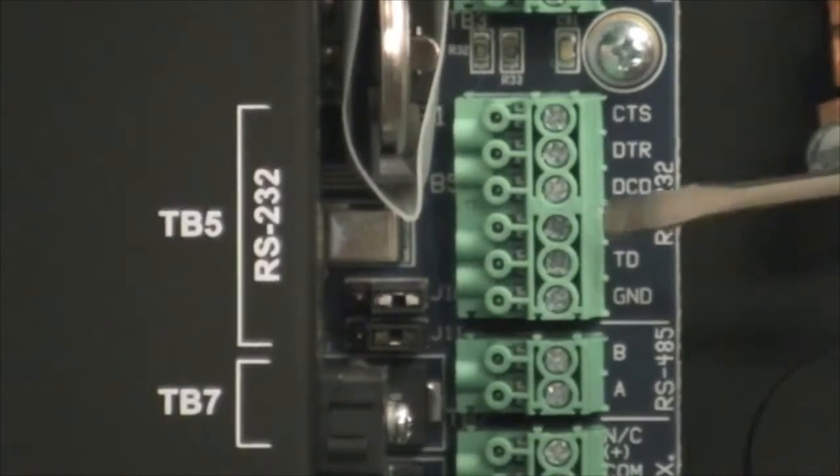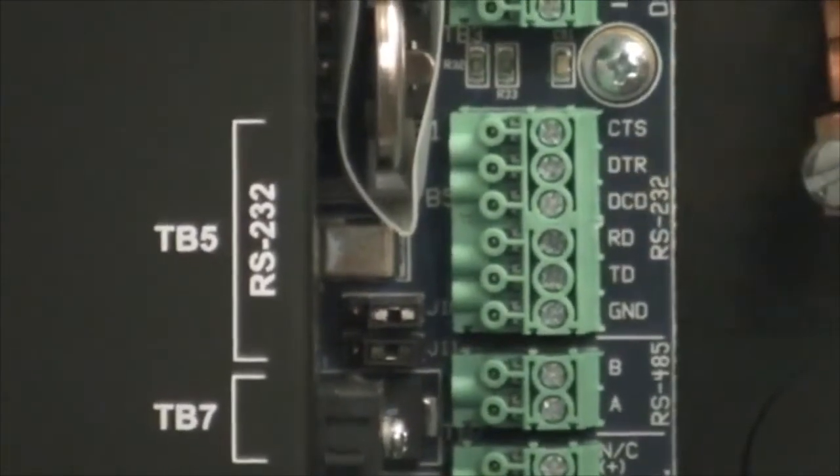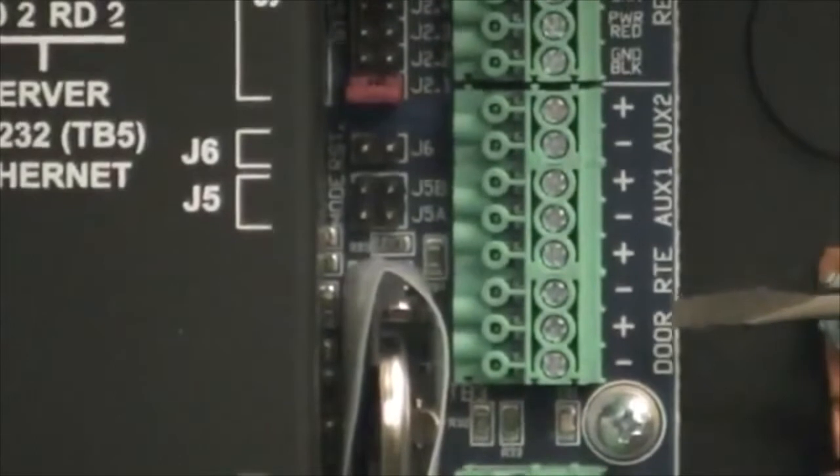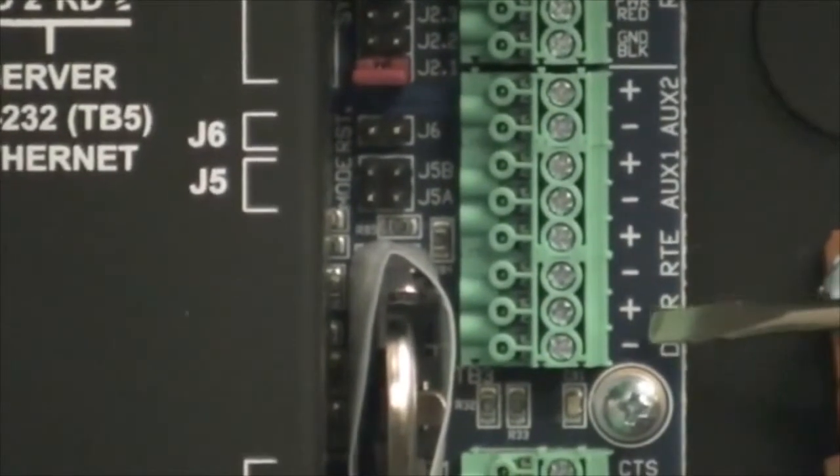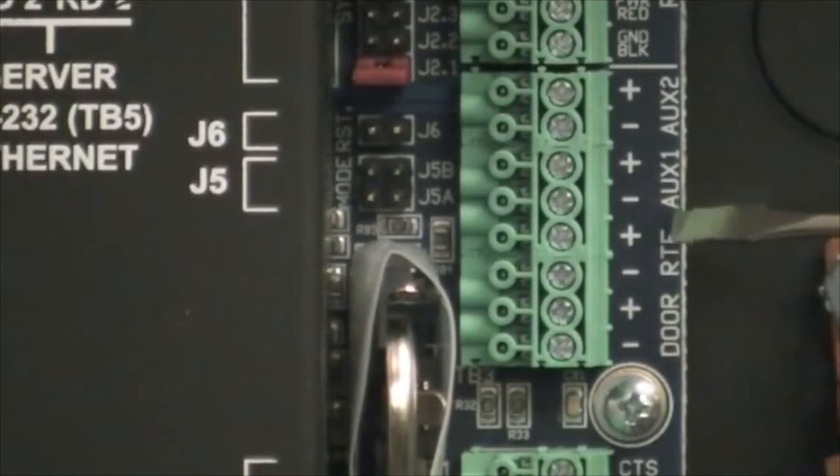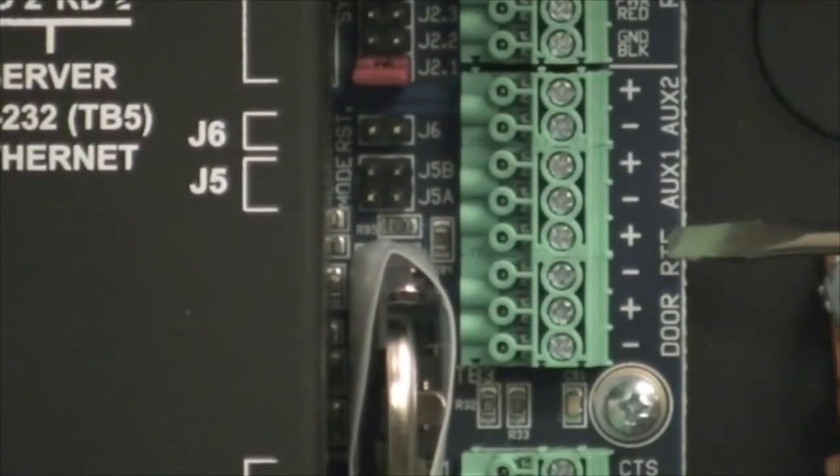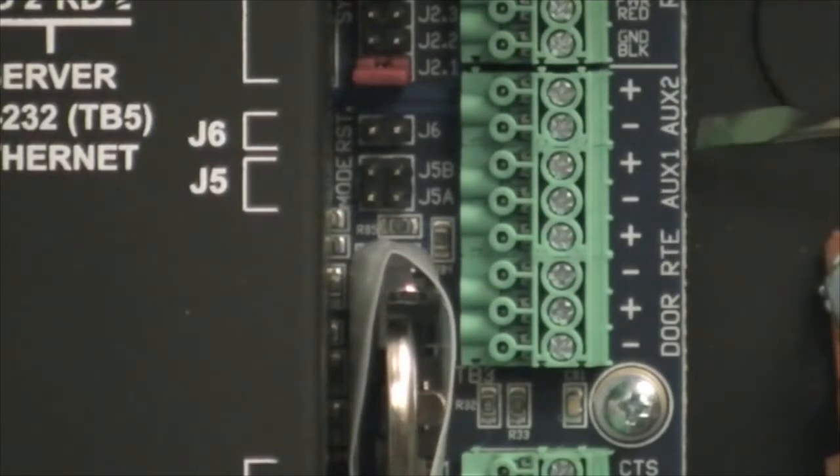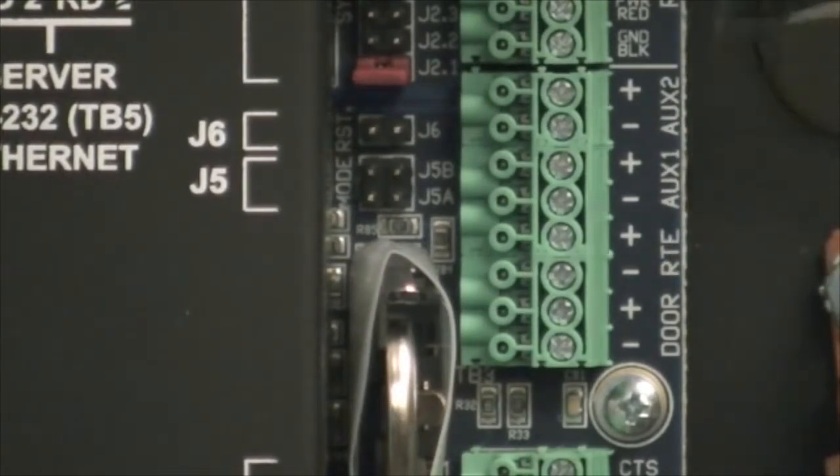Above that, we have all of our door connections, starting with your door contact for monitoring the door position, your request to exit device, which is a normally open contact connection, as well as two additional auxiliary alarm inputs. And above that you have your two reader connections.